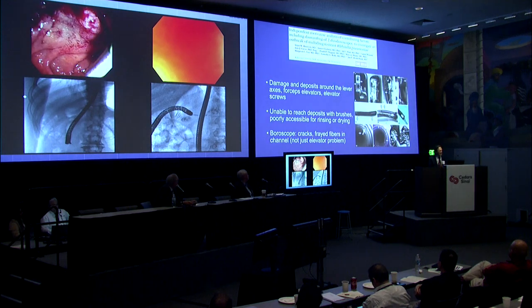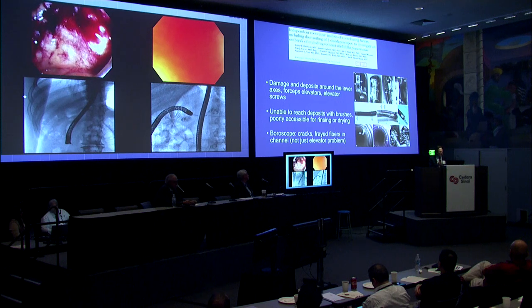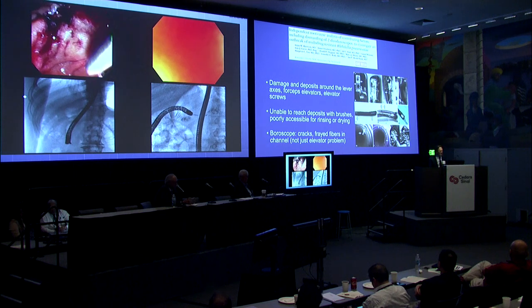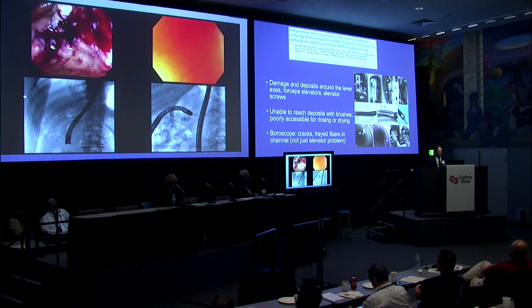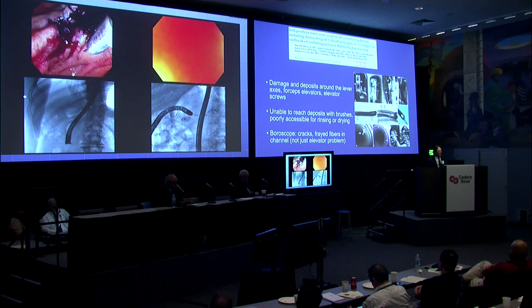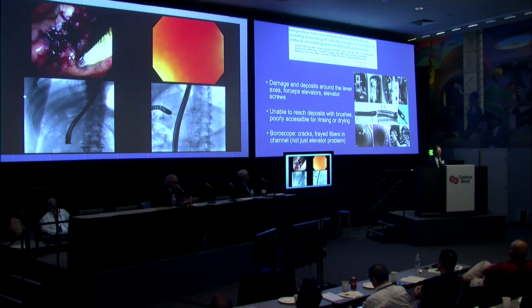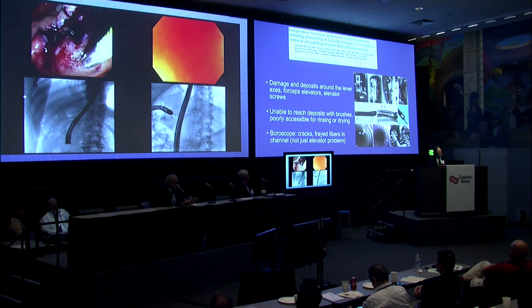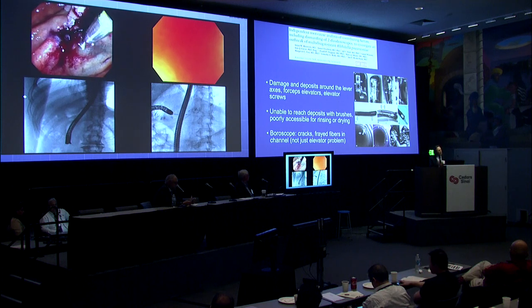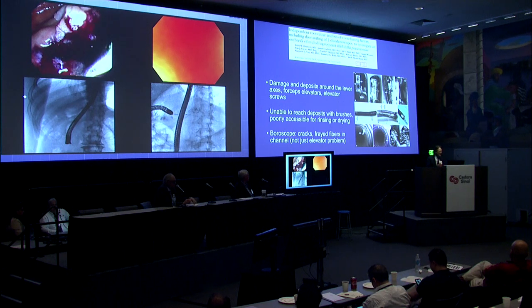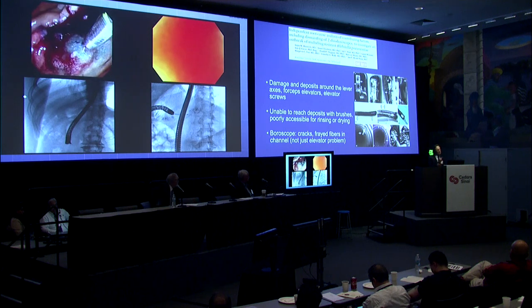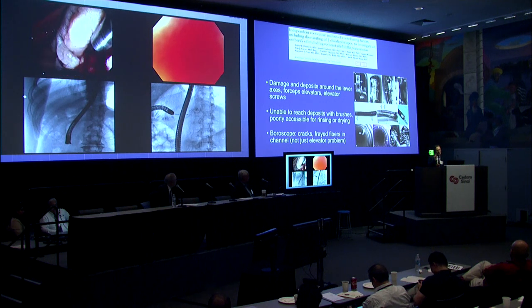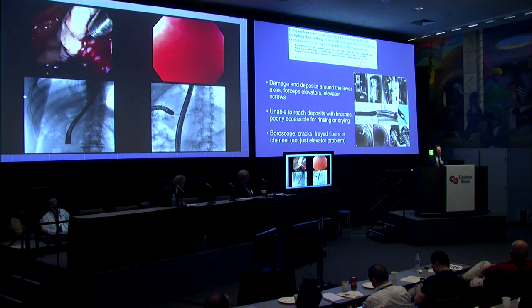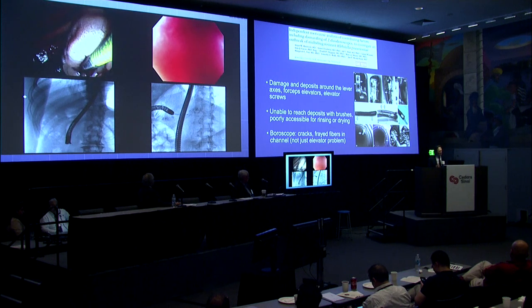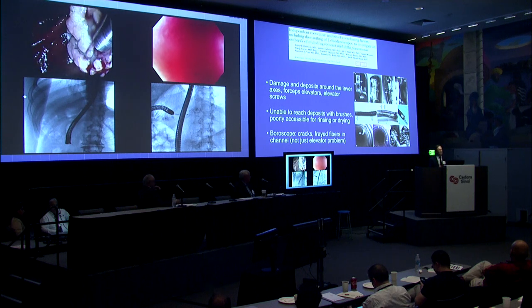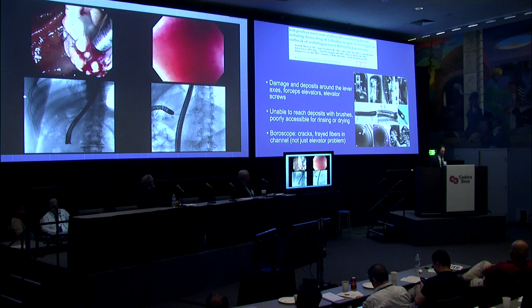So where is the problem actually? We've been hearing about the elevator, and obviously there are lots of nooks and crannies there that are hard to clean. This study from Holland showed damage and deposits around the lever axes, forceps elevator, and the elevator screws. They were unable to reach many of these deposits with brushes, and they were poorly accessible for rinsing and drying. But what's really interesting is if you look at the boroscope picture, where you pass something like a spyglass through the working channel, they're seeing cracks in the working channel and frayed fibers in the channel. So it's not just an elevator problem.